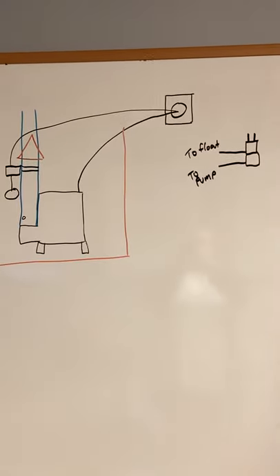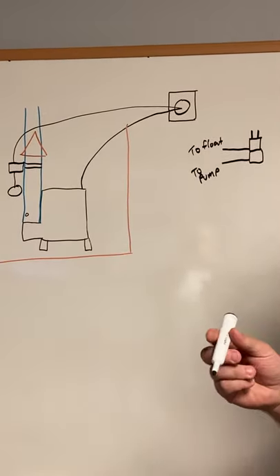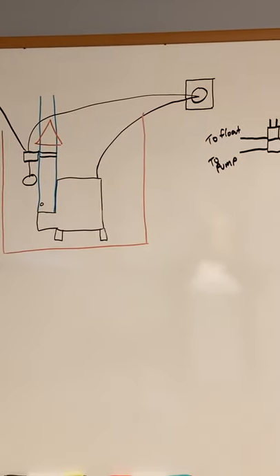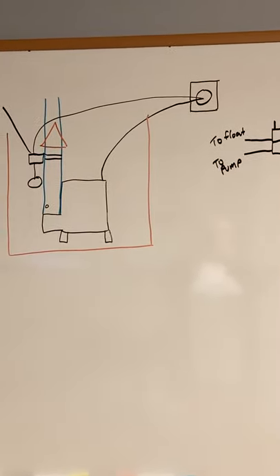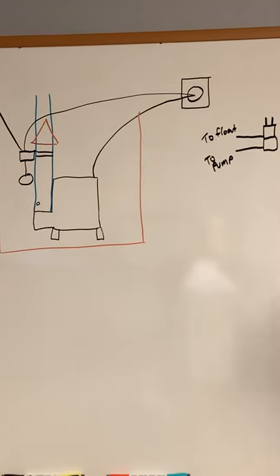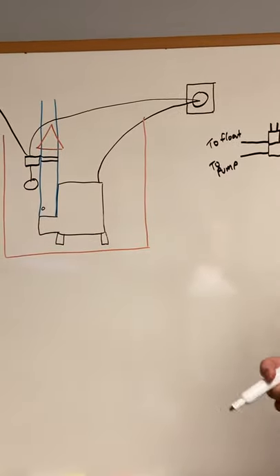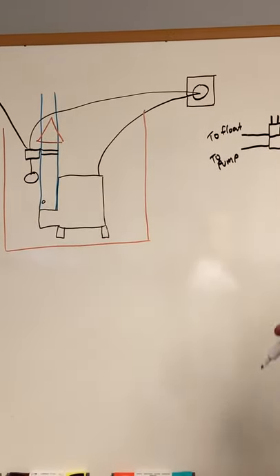So the biggest problem we see with sump pumps are these floats right here. The electric motor normally doesn't go out, however it can, but most of the problems we see are with the switches. Either the switch contacts get wet, they don't make or break anymore, if they get stuck, things like that.